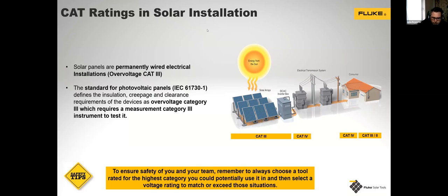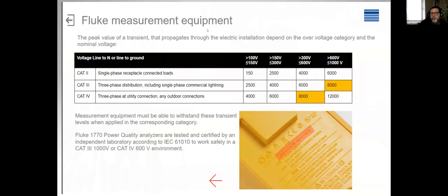It's all to do with overvoltage categories. But put simply, the category rating involves looking at the peak value of a transient. So let's look at category 3. If we've got a 600 volt to 1000 volt Cat 3 system, the maximum peak value is 8000 volts. Whereas in the case of a Cat 2, it's 6,000 volts. So you can see that you need to use the correct equipment for the category area that you're operating in.